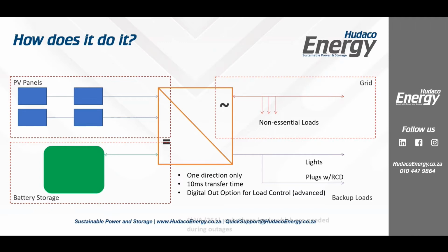So please bear in mind that we can do those, even though we're not going to talk about those today. And then, so this is a 26 amp port. It's for only those loads that are needed during outages. We'll explain more about this side in a moment. We can push this up to 32 amps for about 10 seconds as well to deal with startup loads if you've got motors or something that needs a slightly higher induction load, for example, or startup support.